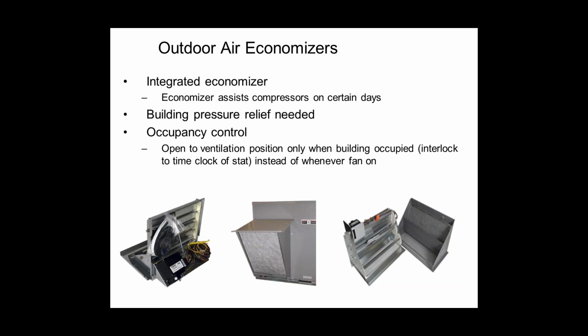It's got two terminals there that are labeled occupancy, and it's saying, put a time clock on me. Tell me when I'm supposed to be on and when I'm supposed to not be on for ventilation. You could put a separate time clock on there, but honestly, no one would ever look at it or change it. So really what you want to do is use a thermostat that has an extra spare output on it, and that output from the thermostat will go up to the economizer controller and tell the economizer whenever the thermostat is in an occupied mode. And we'll do ventilation then. And if it's unoccupied, we won't do ventilation.